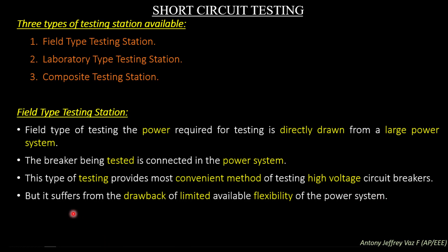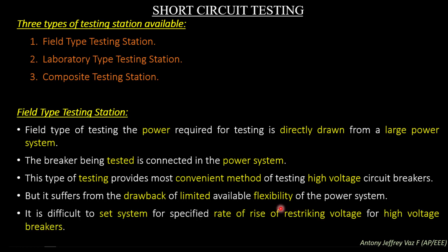Field type testing stations suffer from the drawback of limited available flexibility, since the power system is operating in real time with consumers. The limitations present mean that the flexibility of testing is also minimized. It is also difficult to set the system for a specified rate of rise of restriking voltage for high voltage breakers when using a field type testing station.